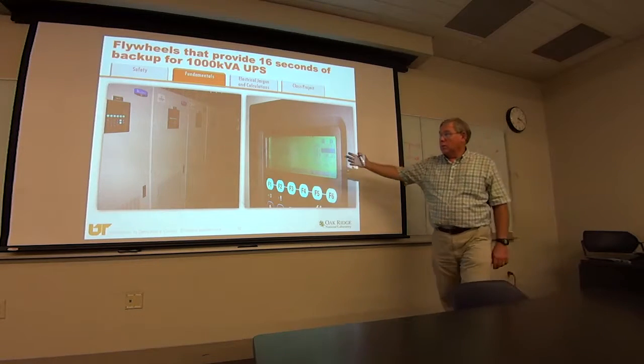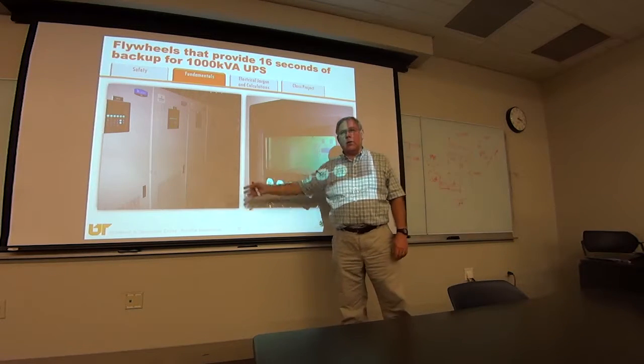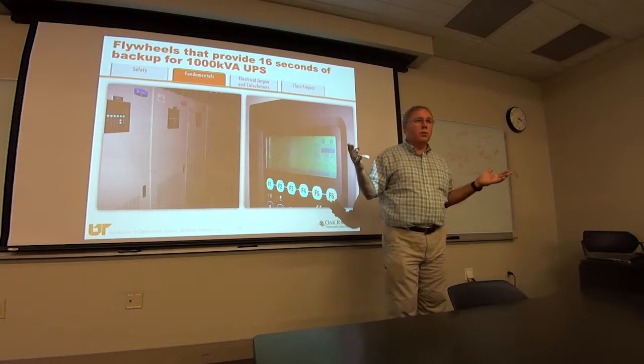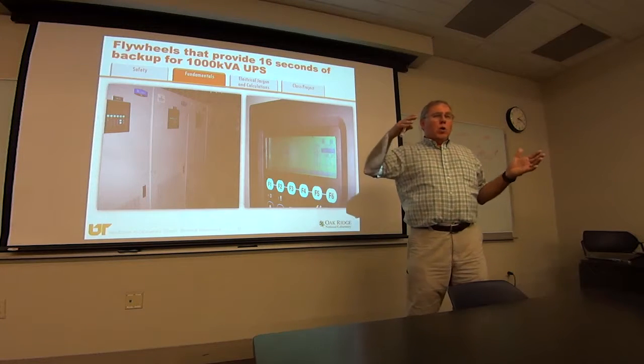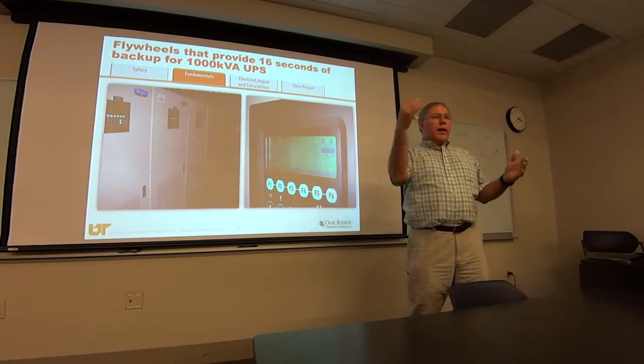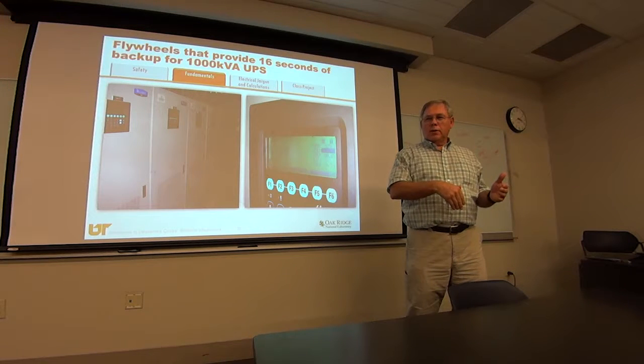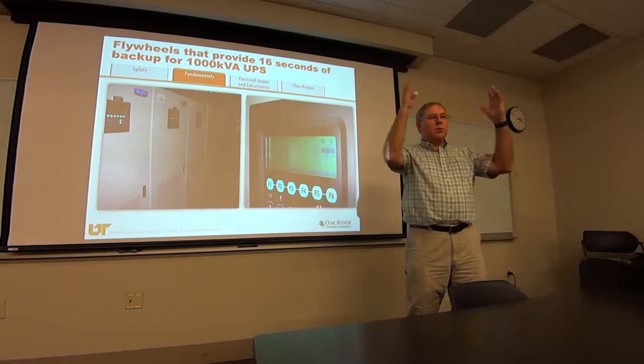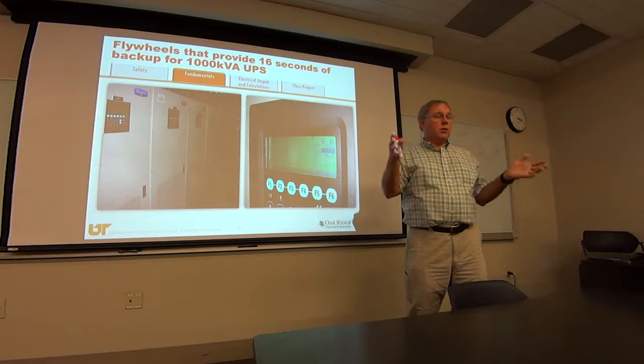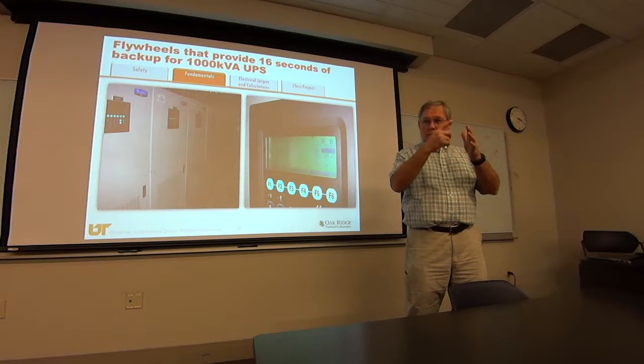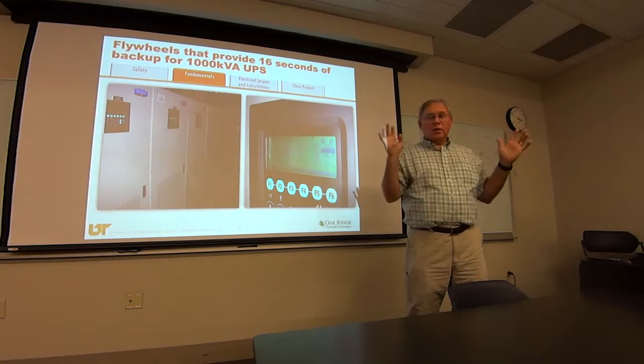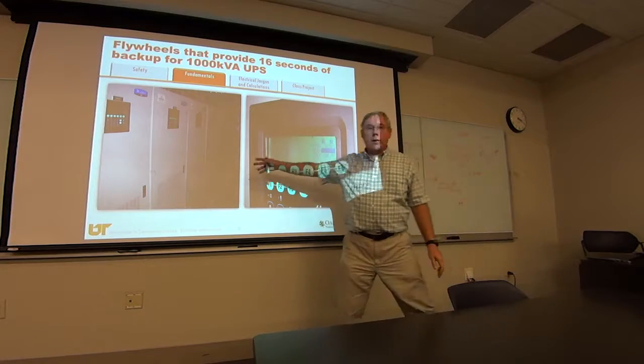But flywheels are good. Now, a generator, a big generator, we got a 2200 kW, 2 megawatt generator, will actually crank and come online in 7 seconds. I mean, it's a monster. It blows smoke out and it shakes the ground, but it's spinning and delivering 480 volts to the UPS in 7 seconds. So you don't need a lot of time.